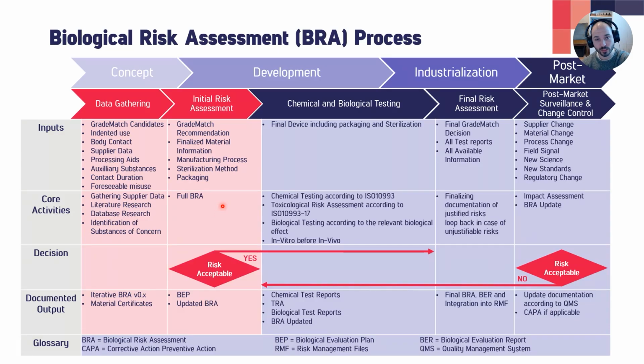And then when you have done that biological risk assessment, there's a decision to be made. Is the risk acceptable or is it not? Do we need more data? Do we need more risk controls? What do we need to do? And if the risk is acceptable, oh, cool, you can skip all of the testing. So the number one learning from this video should be that sometimes you don't even need to test biocompatibility, because you can infer from the data that you have that your device is going to be safe. However, usually this doesn't happen. So you always have some data gaps or some residual risk.